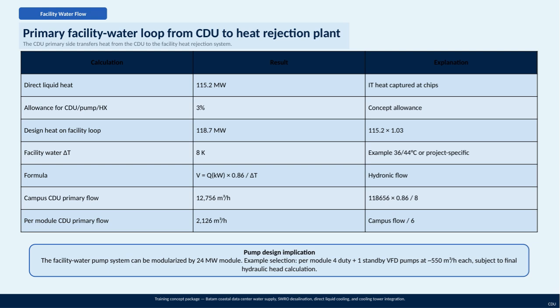Looking at the calculations, the direct liquid heat captured at the chip level is 115.2 megawatts. To account for losses and allowances for the CDU, pump, and heat exchanger, a 3% increase is added, bringing the design heat on the facility loop to about 118.7 megawatts. The temperature difference for facility water is set at 8 Kelvin, which could represent a typical operating range like 36 to 44 degrees Celsius, or adjusted to project-specific conditions.